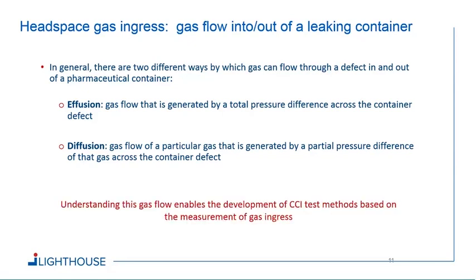What's nice about gas flow is that you can use gas physics to predict how this gas flow will occur. And understanding this gas flow then enables the development of fairly sophisticated CCI test methods which are based on the measurement of gas ingress. And so that's what we will talk about in more detail today.